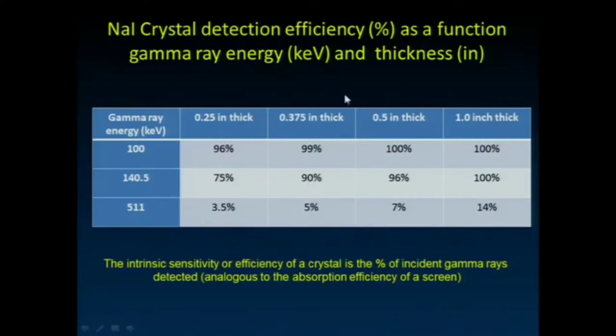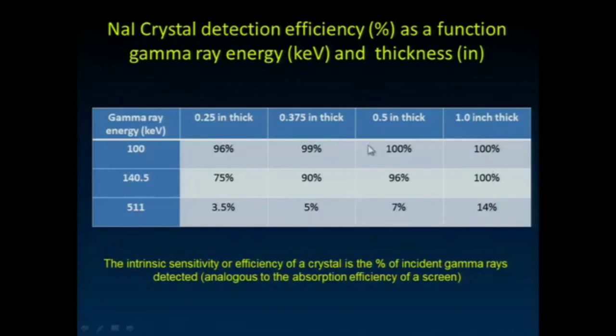Just like with our screens, the thicker we make the crystal, the more room there is for light to diffuse and the worse our resolution properties become. So we don't want to make the crystal thick just for greater stopping power. The three-eighths inch thickness is a nice balance between resolution properties while still stopping the majority of the technetium-99m photons.